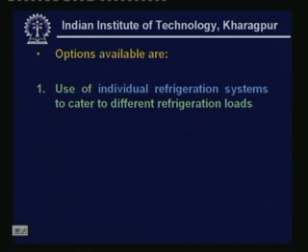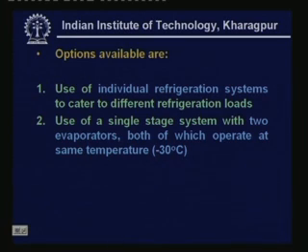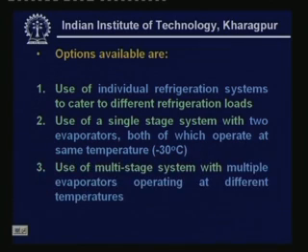The options available are: number one, use of individual refrigeration systems to cater to different refrigeration loads — meaning two individual systems, one for the very low temperature requirement and one for the high temperature requirement. The second alternative is to use a single-stage system with two evaporators both operating at the same temperature, i.e., minus 30°C. The third option is to use a multistage system with multiple evaporators operating at different temperatures.